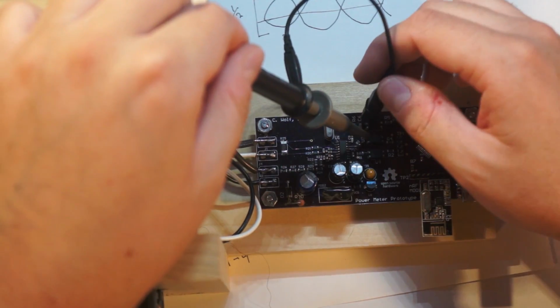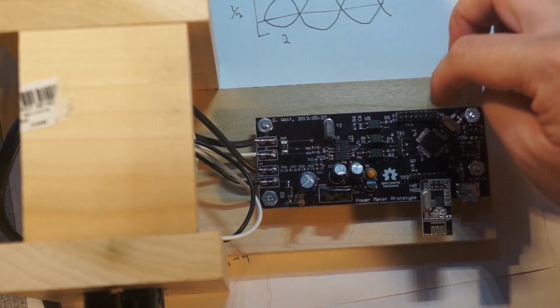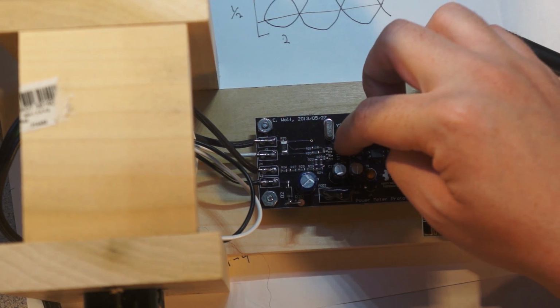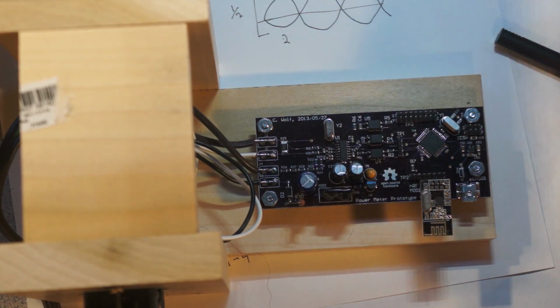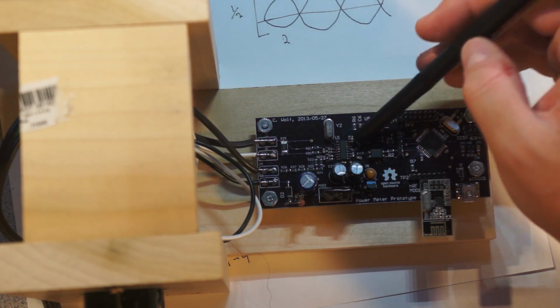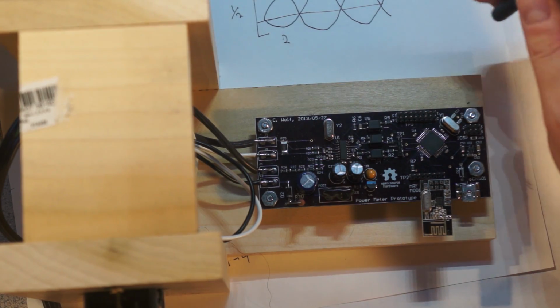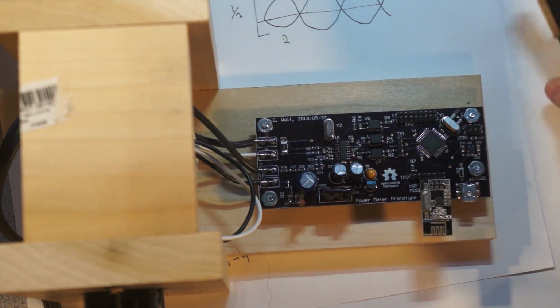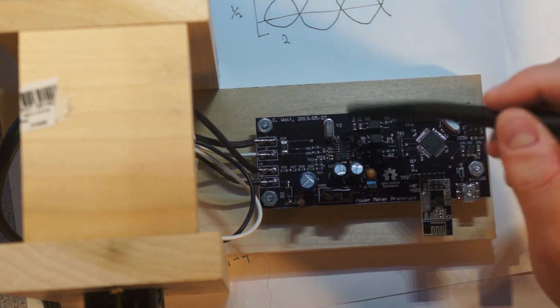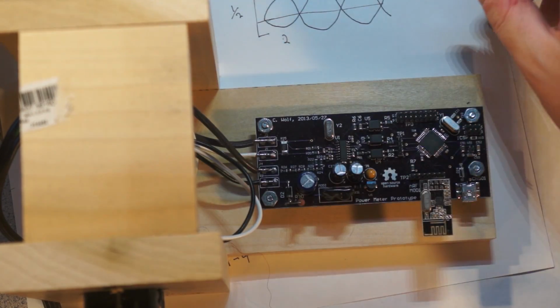I can clip onto these points and actually look at them. If you don't have an isolation transformer, there's no way to really do any sort of verification on this side, which is actually what happened, mostly because I somehow read 9600 baud as 600 baud, but that's another story of me being derpy. Again, any measurements in this section of the circuit at all have to be done on the isolation transformer.